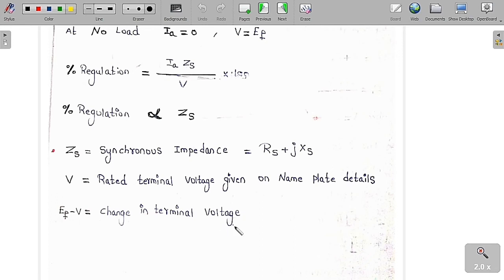So one important formula to always analyze: the percentage regulation of the alternator is EF minus V divided by V, into 100, where EF is the EMF induced per phase in the stator coil, and V is the rated terminal voltage given on the nameplate details. So EF minus V is nothing but IA into ZS, and the percentage regulation is always proportional to the synchronous impedance.